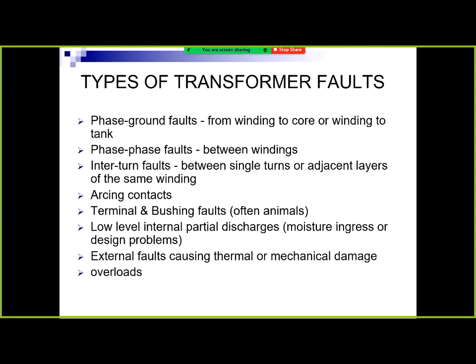We had some problems 20 years ago where AEMO wouldn't allow us to take an outage. It was actually NEMMCO in those days. Wouldn't allow outages. We want to take a transformer out. We've got 2 transformers sitting there. They say one could trip, the load will drop onto the other one, and we go, yeah, all right. The load at that site peaks at 200 MVA. It's typically 150. This time of the year, it's only 120, and that transformer's got an overload capacity to 120. They still wouldn't allow us the outage.